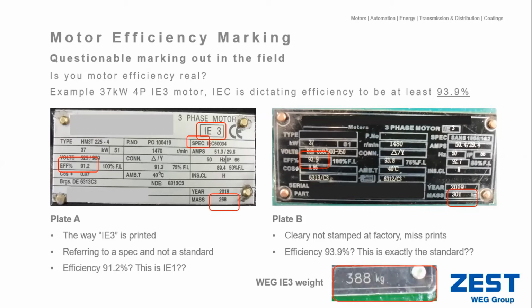If you look at the nameplate on the left, you'll see at the top it says IE 3 and refers to a spec. It's not a spec, it's a standard that we need to comply with. And on this motor on the left with the silver nameplate, we also see that the efficiency rating is stated at 91.2%. Although if we look at the standards, a 91.2% efficiency is actually an IE1, or as we refer to it, a standard efficiency motor.